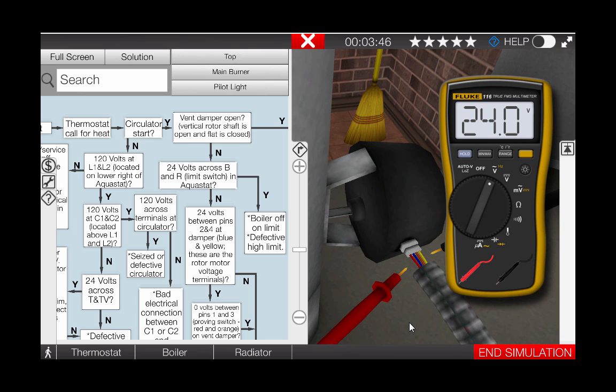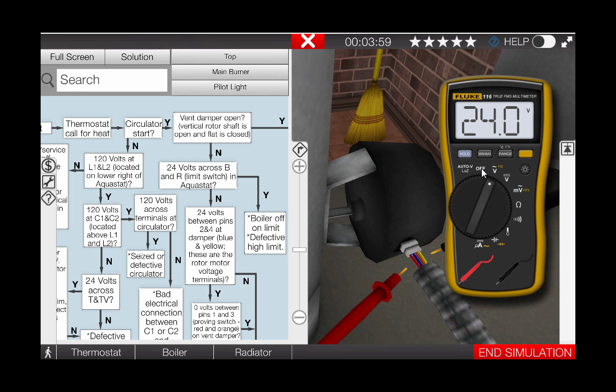So what we have here is we have 24 volts available to the motor, yet the end switch is not closing and proving that the motor is energized. This verifies that the motor is faulty in the vent damper and needs to be replaced.